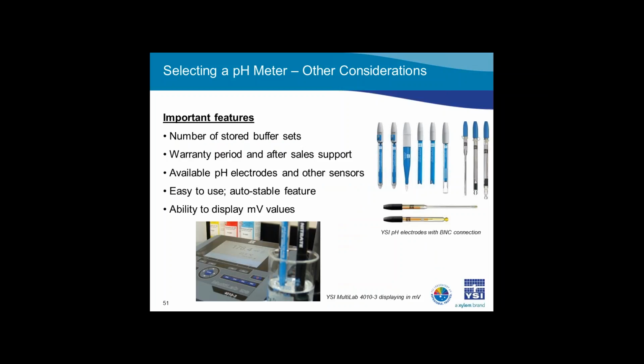Some instruments have many stored buffer sets within the instrument's memory. Since buffer sets can have different temperature profiles and buffer values, selecting the exact buffer set you have will ensure an accurate calibration result. Since lab instruments should last a long time, please consider the meter warranty period and the quality of the company's technical support. This will be very important if you ever have an issue with the meter.